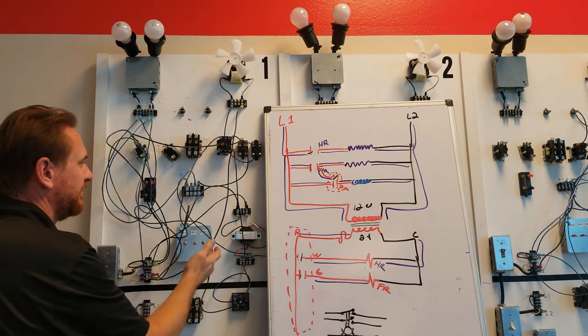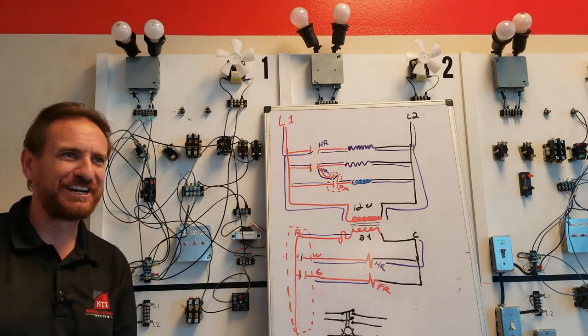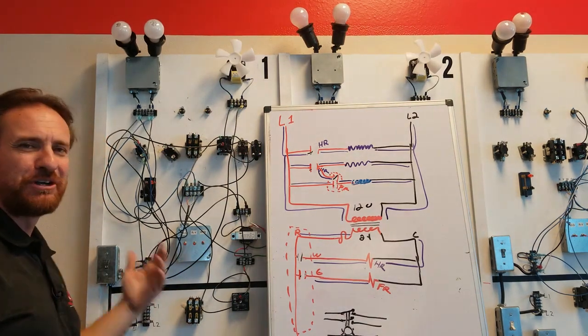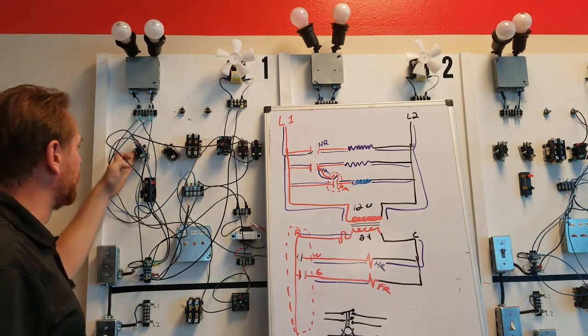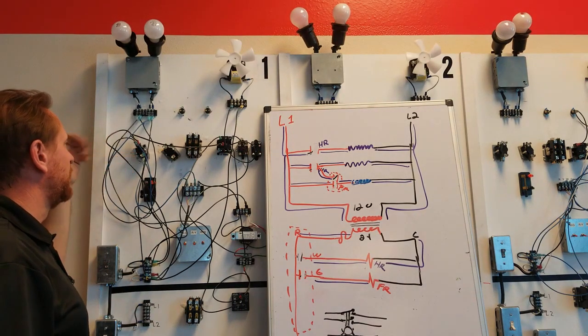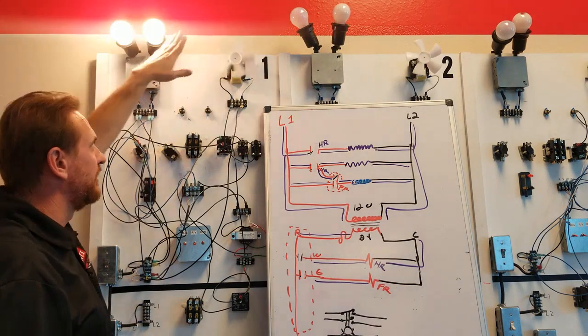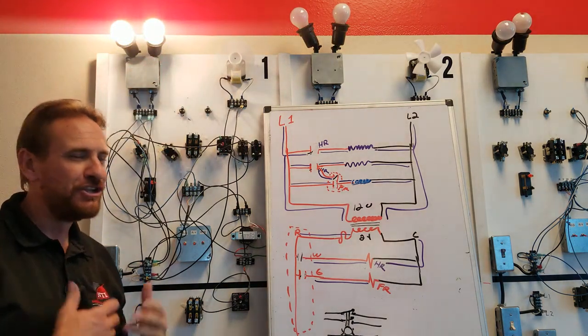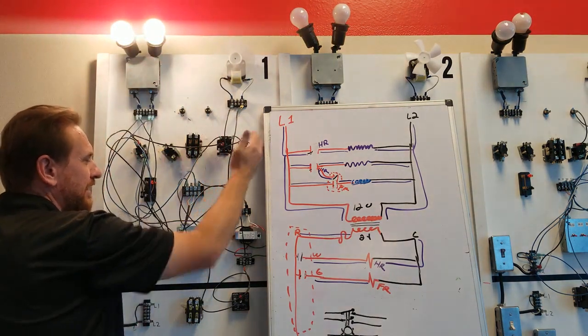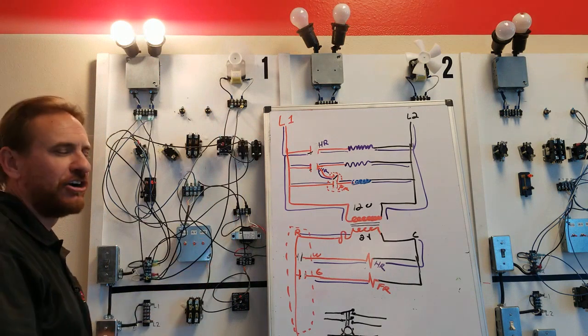We have a call for heat. Oh no, the heater did not come on. Now we should panic. Now we're going to wait for that thermal time delay relay. This is getting warm right here. Once this warms up enough, we're going to close that switch on, and on, just like that. No difference in operation between this relay and this relay. We satisfy our call for heat.